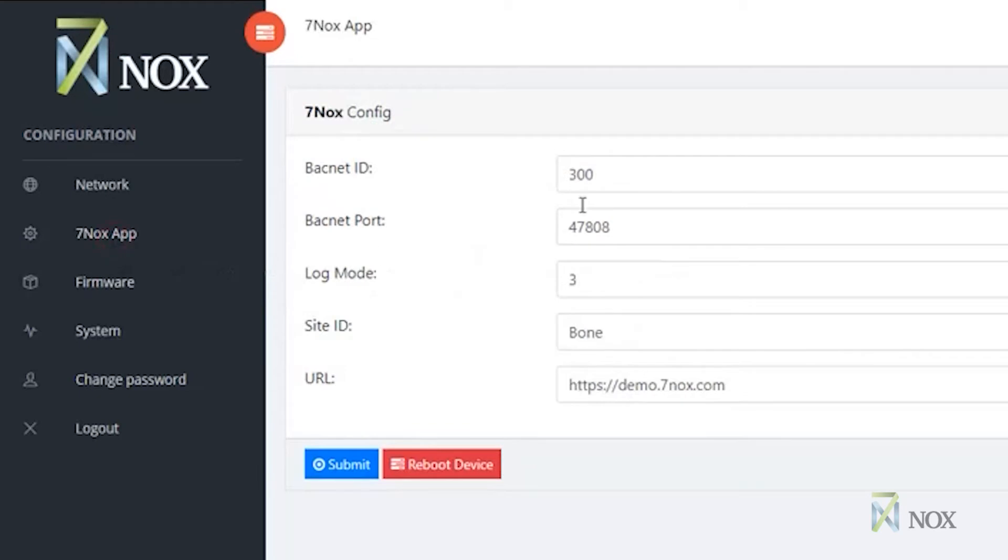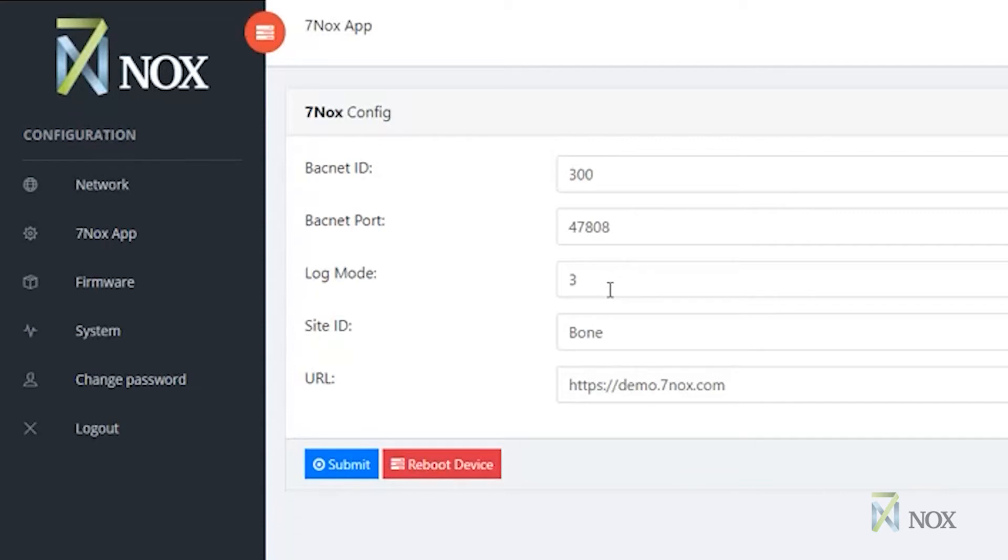In the 7NOX app tab, you are able to configure the BACnet ID, BACnet port, and log mode, which by default is set to 3, which records all activities in a flat file. One and two record less information but is not recommended. Site identification and URL are provided by the 7NOX support team at the time of implementation. Site identification is a unique ID. The URL is the HTTP connection to the 7NOX hosted service.